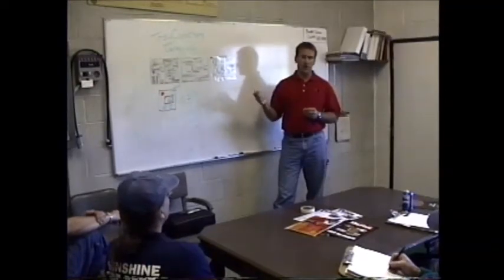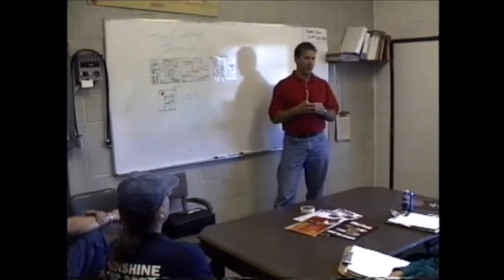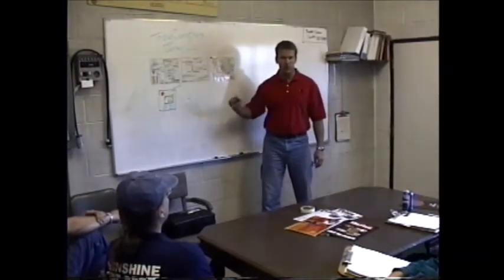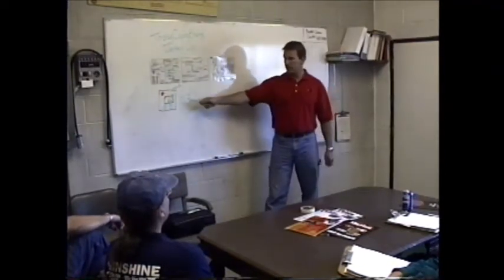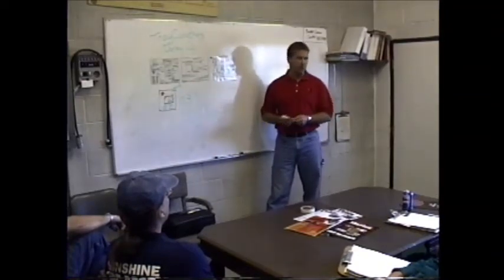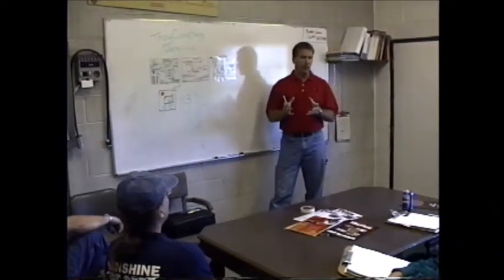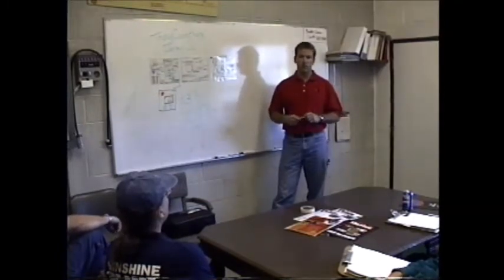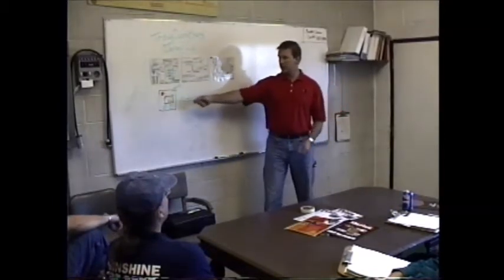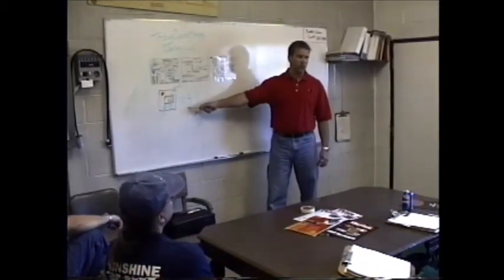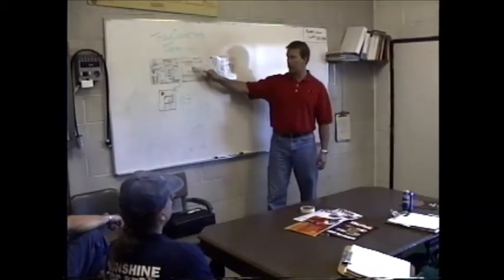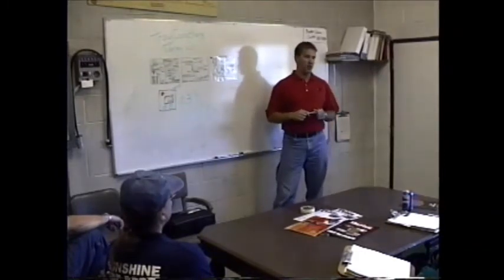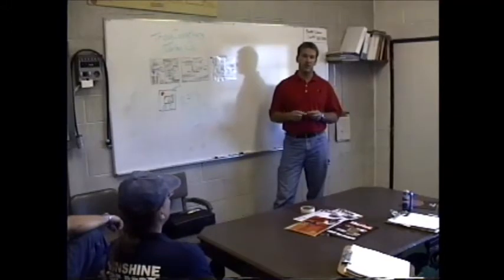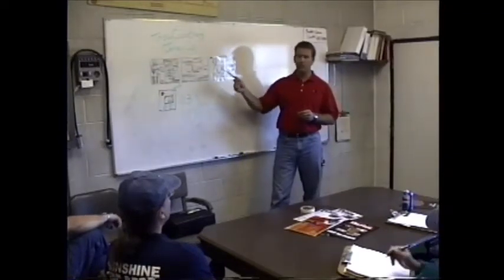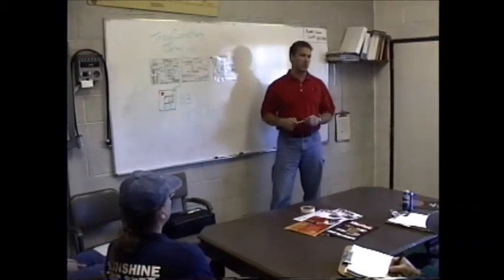Now that same 60 CFM of air, if we increase that water volume from 25 or 30 gallons a minute, and we can see all that right on this display as we open and close our lever, as we open that valve a little bit more and get it up to about 60 GPM, along with the 60 CFM of compressed air, now we've got a really high velocity, milkier, wetter type of foam, but it's a high velocity foam that's going to really absorb a lot of heat and knock down a lot of fire. That's 60 gallons a minute, coupled with 0.3% of Class A foam, along with that 60 CFM of air that we trip with this switch when we turn on the air, and it's going to come out of that nozzle in a hurry. It's going to knock down as much fire and absorb as much heat as about 200 GPM of plain water through a fog nozzle at 150 PSI. So that type of heat value can be knocked down with only 60 gallons per minute of water leaving your truck.